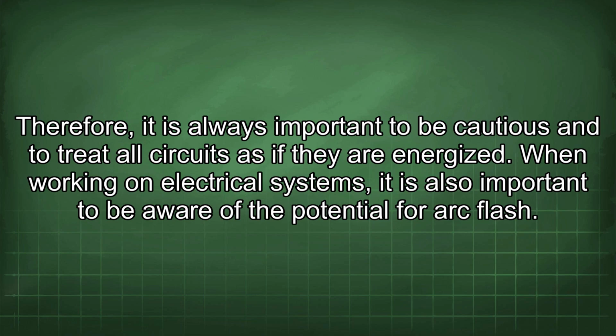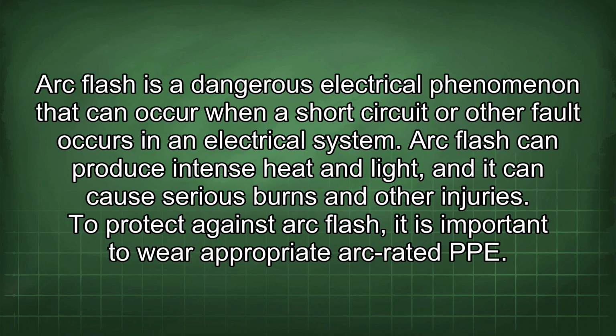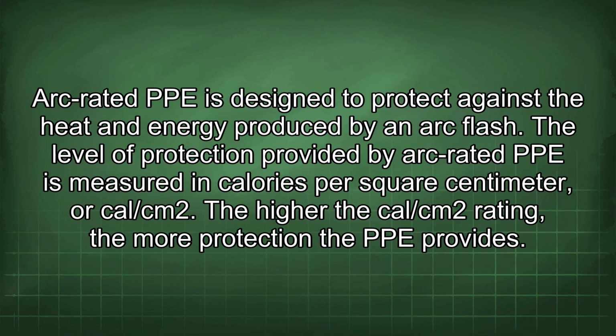When working on electrical systems, it is also important to be aware of the potential for arc flash. Arc flash is a dangerous electrical phenomenon that can occur when a short circuit or other fault occurs in an electrical system. Arc flash can produce intense heat and light, and it can cause serious burns and other injuries. To protect against arc flash, it is important to wear appropriate arc-rated PPE. Arc-rated PPE is designed to protect against the heat and energy produced by an arc flash. The level of protection provided by arc-rated PPE is measured in calories per square centimeter, or cal/cm². The higher the cal/cm² rating, the more protection the PPE provides.